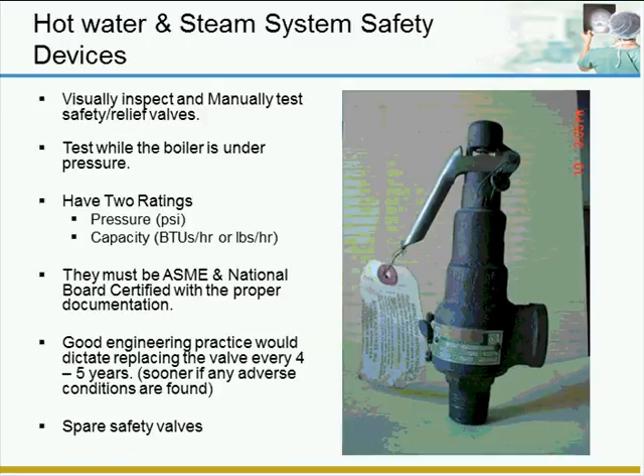Safety devices on steam systems. Safety relief valves are maintained on all boilers and steam systems to prevent the units from overpressurizing. They are rated in pounds per hour and pounds per square inch. Pounds per square inch will be the set pressure rating, and the capacity rating will be your pounds per hour. If you look at the picture, you have a nameplate there, and you will have an ASME and National Board stamping on the safety valve. All valves in the U.S. jurisdictions are required to be stamped ASME and National Board.